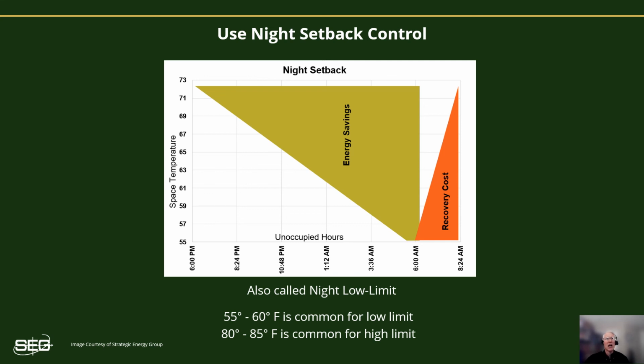Each air handler needs to have its own optimal start time and warm-up parameters set up properly in order to function optimally. Frequently, I see these energy-saving features installed and enabled, but when we look at the trend logs, we see they're not working properly. More often than not, it's because they've never been tuned or set up properly with the actual parameters for the building and or the systems that they're controlling. While this should be a function that takes place during the installation and commissioning of any new control systems, you may never know what your systems are doing unless you actually go out and check each of these air handlers' operations to see what they're doing.